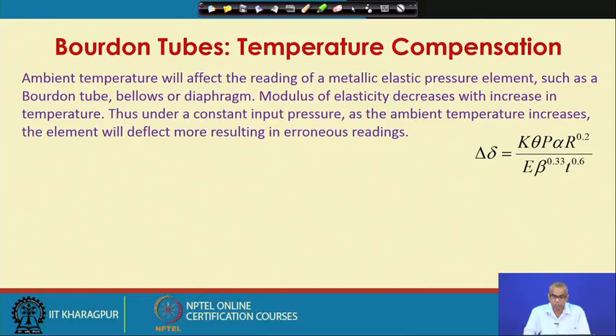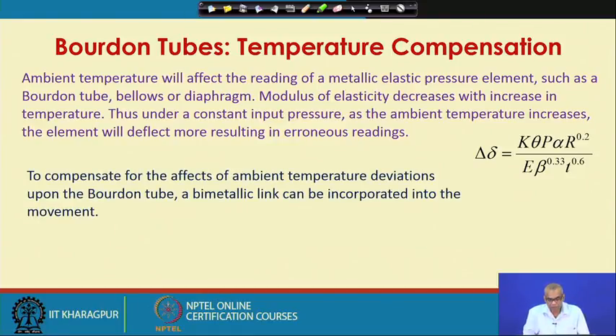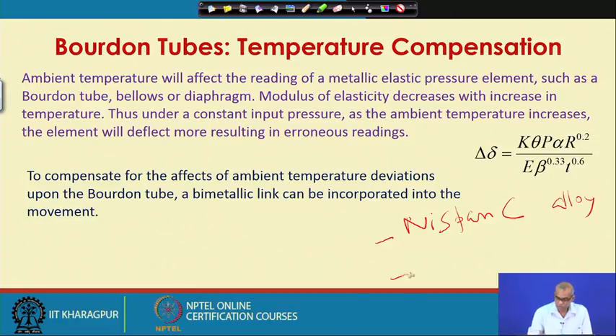Thus, under a constant input pressure, as the ambient temperature increases, modulus of elasticity decreases and the element will deflect more, resulting in erroneous reading. You can see it from the equation also. So, to compensate for the effects of ambient temperature deviations upon the Bourdon tube, a bimetallic link can be incorporated into the movement. So, one solution is use of Nispan C alloy. Another is to make use of a bimetal. A bimetal is made of two metals and they have different expansion coefficients. So, you take two different metallic strips and they are rigidly bonded.